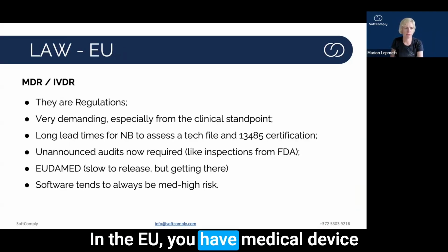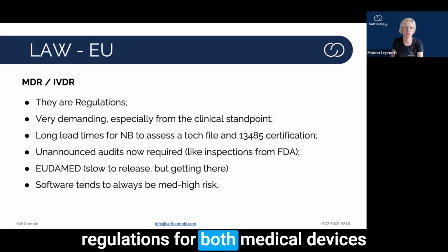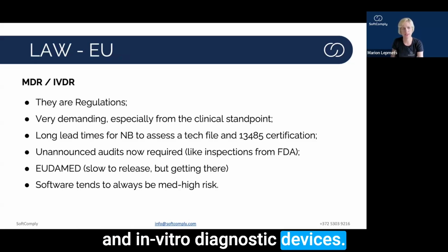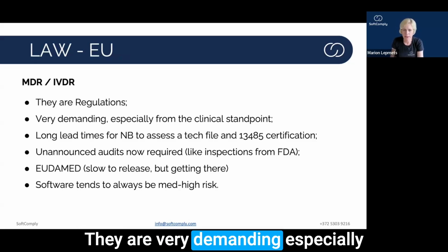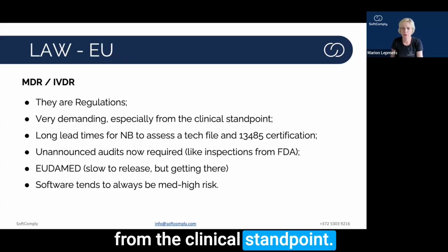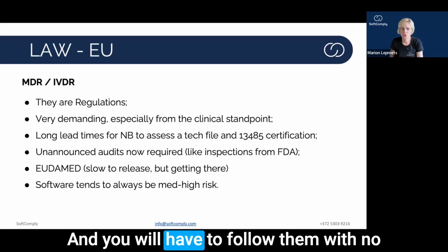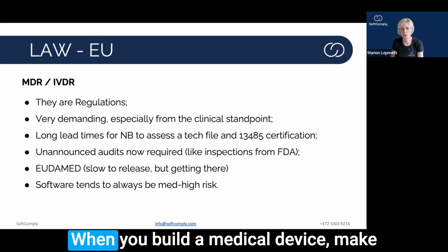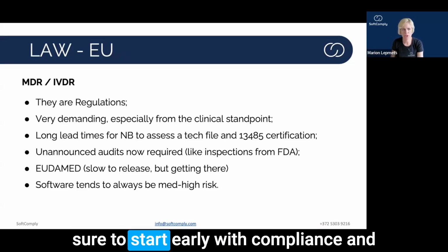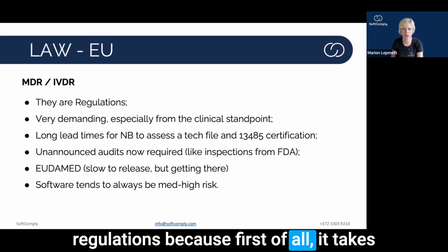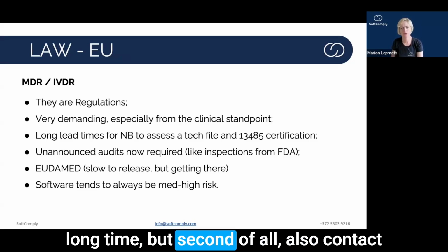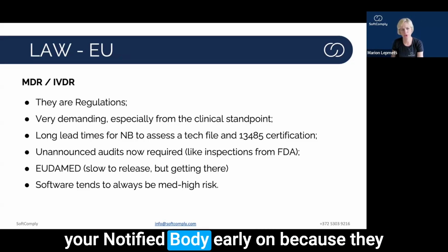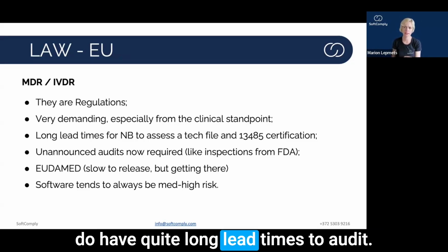In the EU, you have medical device regulations for both medical devices and in vitro diagnostic devices. They are very demanding, especially from the clinical standpoint, and you will have to follow them with no interpretation left for individual countries. When you build a medical device, make sure to start early with compliance and regulations because, first of all, it takes a long time, but second of all, also contact your notified body early on because they do have quite long lead times to audit.